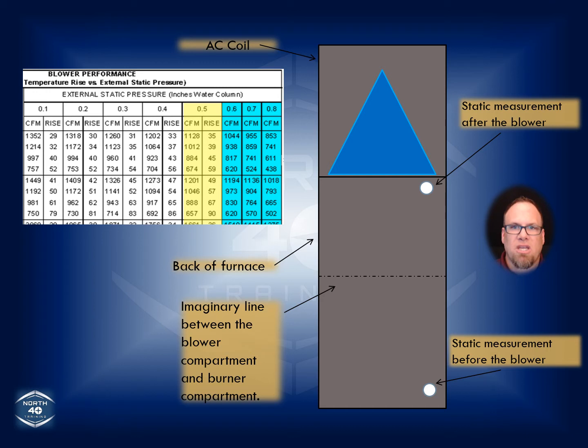Now, if you look at where the two white holes are in this furnace, they could be symbolic of the side of the furnace or the back of the furnace. You could make those two penetrations actually in different spots. I've seen people, and I myself have gone in through the high limit switch, removing the high limit switch. We're not running this on heat or cool. We're only using the fan on auto speed, or potentially just setting up dip switches. So you could go in through the high limit switch, and I've seen people go in before the blower section with taps that go in through the low voltage side of that cabinet. So there are other places that you could go.